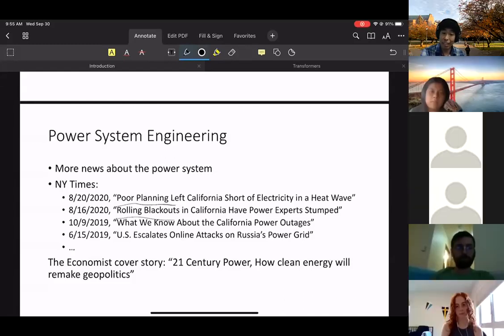No, it's actually more. The quality of service we try to get to is every 10 years. So the expected loss of power is that every 10 years, each customer will lose 1 hour of power. And this is actually the standard. If you don't meet this, you actually get a penalty from the government. NERC, the North American Electric Reliability Corporation, comes and penalizes the utility if you lose power more than 1 hour every 10 years on average. Nobody on the West Coast is meeting this right now. We're very far from meeting this number.